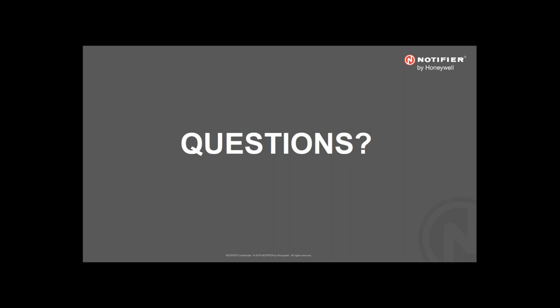Let's see. I'll start from one of the later subjects you were talking about in your presentation, low-frequency notification and the different scenarios and requirements there. So starting off, I wanted to ask you broadly, are low-frequency sounders required in all jurisdictions now? So it depends on the version of NFPA and IBC that has been adopted in that jurisdiction. But currently, there are only 7 states that have not adopted low-frequency in some form. All other jurisdictions either have some form of low frequency, or they have regional adaptation for low frequency sounders.